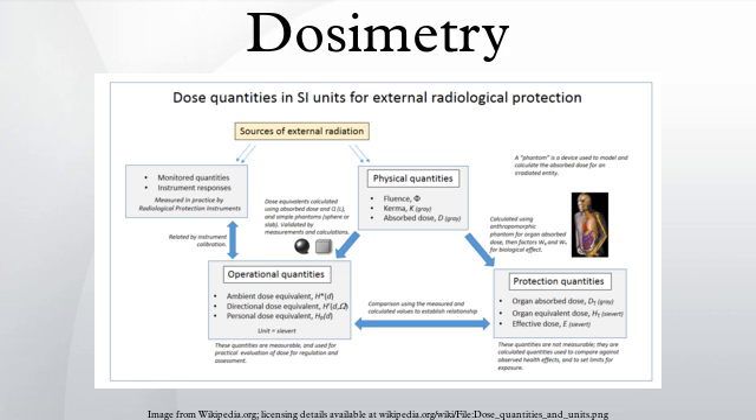There are several ways of measuring absorbed doses from ionizing radiation. People in occupational contact with radioactive substances or who may be exposed to radiation routinely carry personal dosimeters. These are specifically designed to record and indicate the absorbed dose received. Traditionally these were badges containing photographic film, which would be chemically developed following exposure to indicate the total absorbed dose received. Film badges have now been largely replaced with other devices such as the TLD badge which uses thermoluminescent dosimetry or optically stimulated luminescence badges. A number of electronic devices known as electronic personal dosimeters have come into general use using semiconductor detection and programmable processor technology.